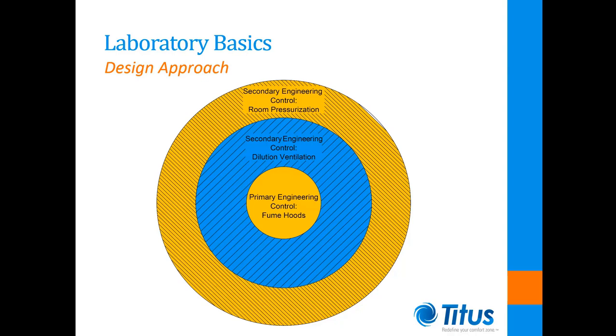Alternatively, a proportional offset control can be implemented where the differential is a percentage of the total exhaust airflow. There are some exceptions to this where the pressure relationship will need to be positive in order to prevent contaminants from outside the room affecting the experimentation. These spaces are typically microelectronic or medical laboratories where the air cleanliness is critical to ensure accurate results of the testing or medicines being developed.